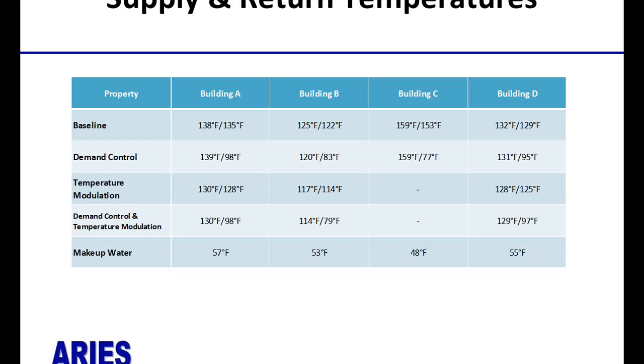So here we have the supply and return temperatures for all 4 buildings for all the test cases. And this is what's going to drive any kind of savings that you'll achieve, either in reduced temperature at the tap or reduced radiative losses along the recirculation piping. I think there should be two of these for temperature modulation. We set set points of 110 and 125 degrees, and these are obviously well above that, and that brings to bear some commissioning issues that we'll talk about in a little bit. And this obviously, there were some savings associated with these 2 buildings, but not as much as could have been optimized.